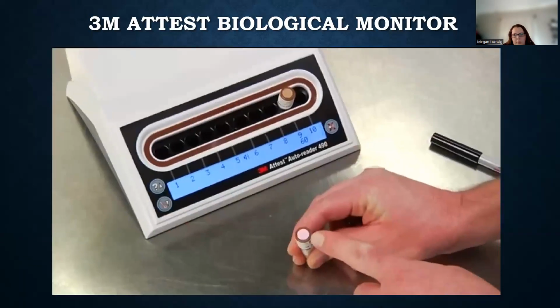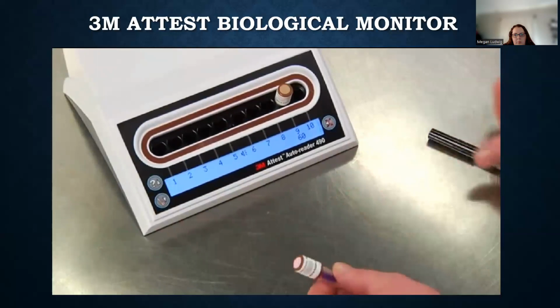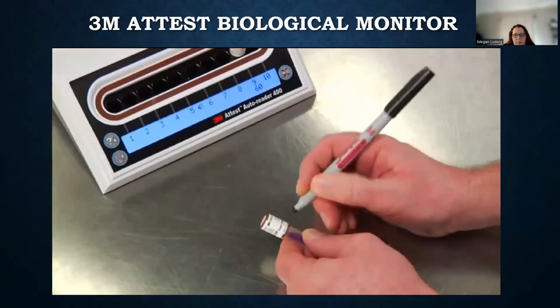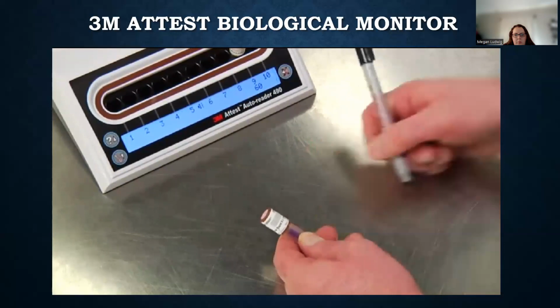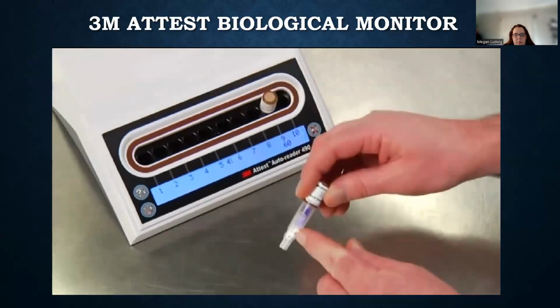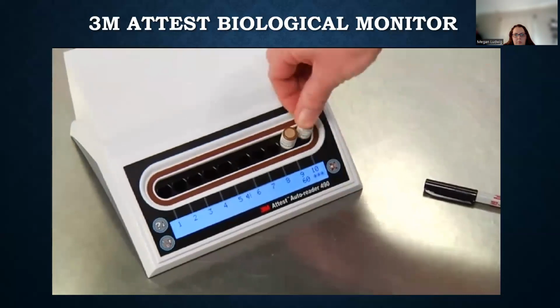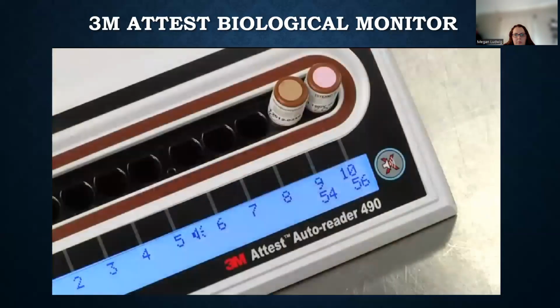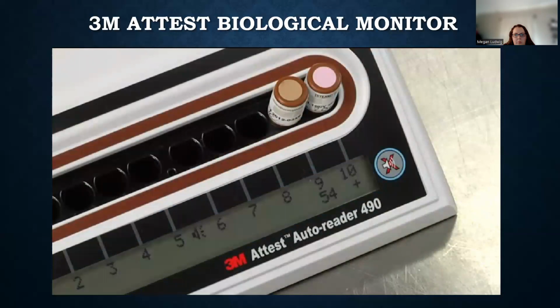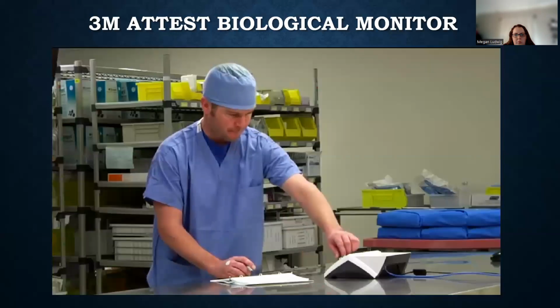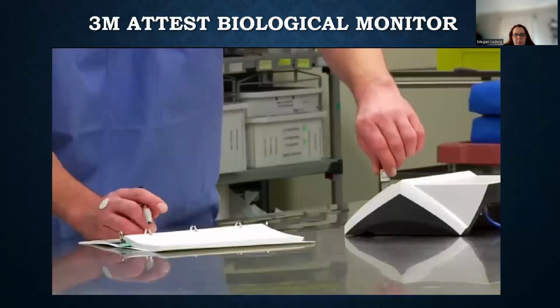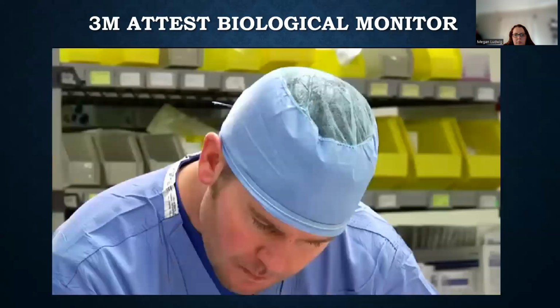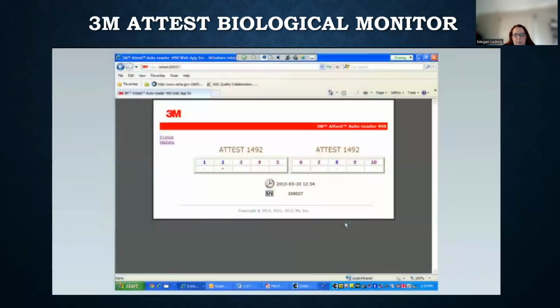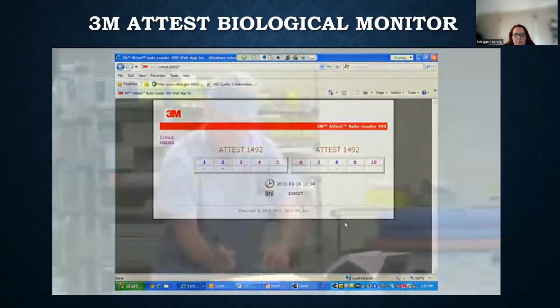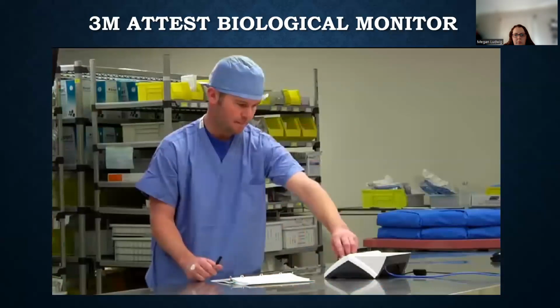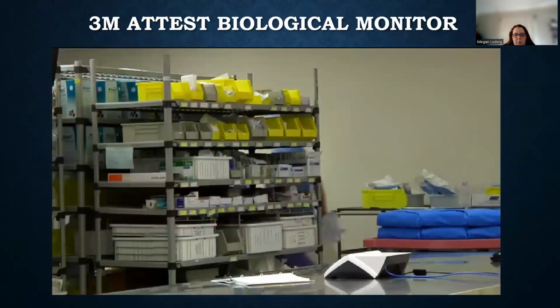Each day that a processed 1492 VBI is incubated, activate and incubate an unprocessed 1492 VBI as a positive control. The positive control should be from the same lot code as the processed biological indicator. The positive control BI should provide a positive fluorescent result. After a BI test is complete, the next step is to record your results. You can use traditional record-keeping methods or the 3M Attest™ Auto-reader 490 web app. The 1492 VBI is normally discarded after the fluorescent result has been recorded.